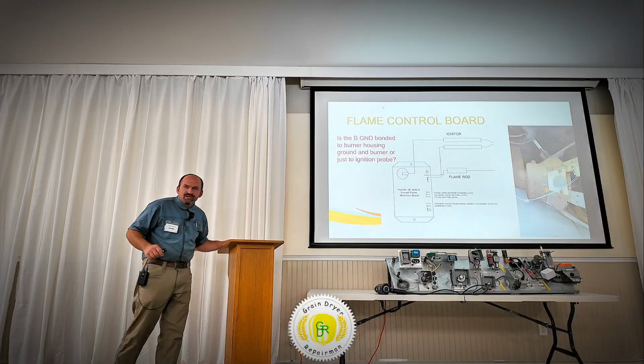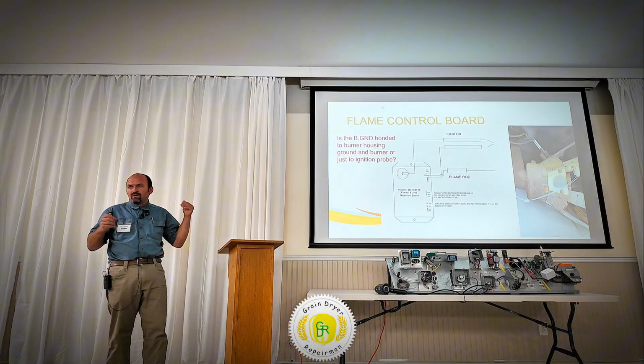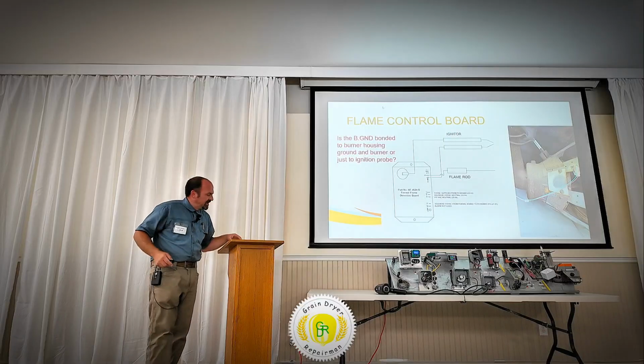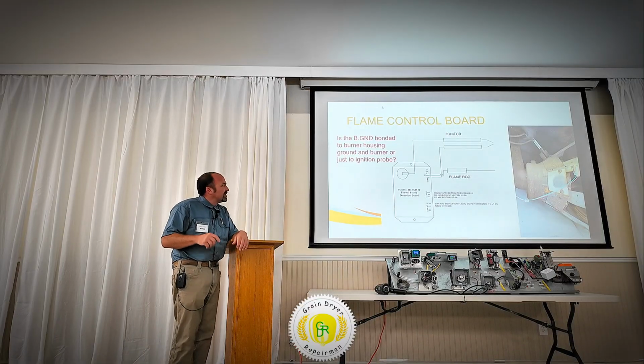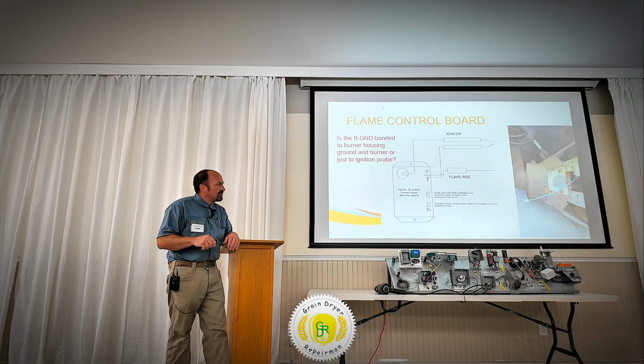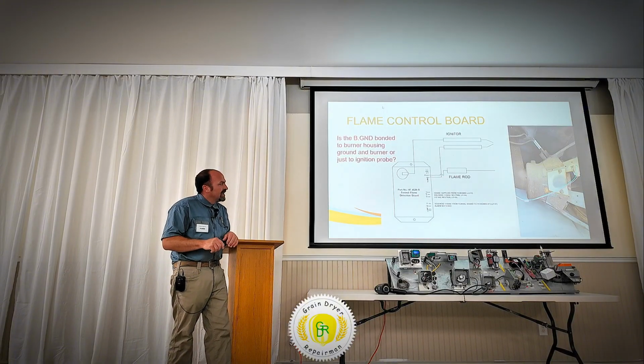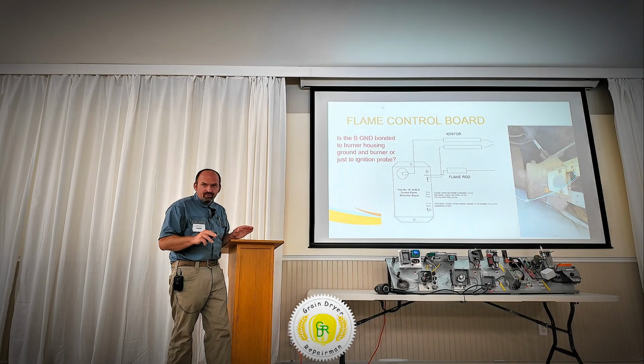I don't know how many of you are electricians or understand electrical work or how wiring should be done. This wiring diagram is from their manual and shows how they are wired. This is B ground. This should be connected to the burner and the ground. If you look at the Fenwal manual, this wire goes to the ignition probe. On a brand new dryer, and on an older dryer, it goes to the ignition probe. This wire needs to be bonded to the ground.